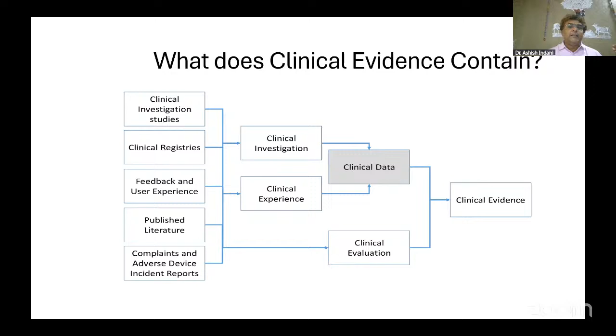These processes are interconnected, while data comes from clinical investigation and clinical experience. But in the background, the clinical investigation studies, the clinical registries, feedback, user experience, published literature, and the complaint and adverse device incidents feed into both clinical data and clinical evaluation. Finally, we make clinical evidence. So at large, the clinical evaluation report is the most critical documentation at the clinical level, of the clinical module of a medical device.